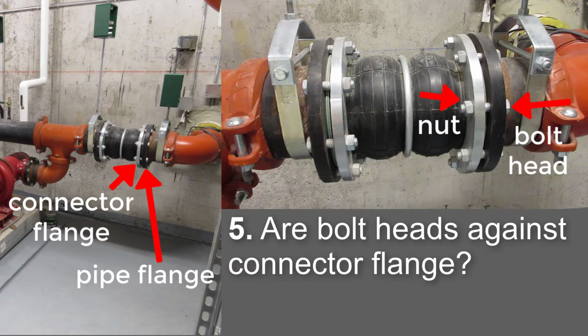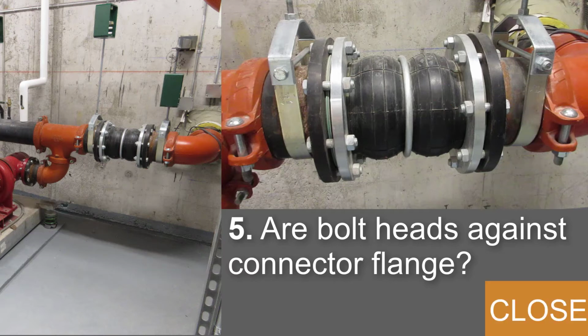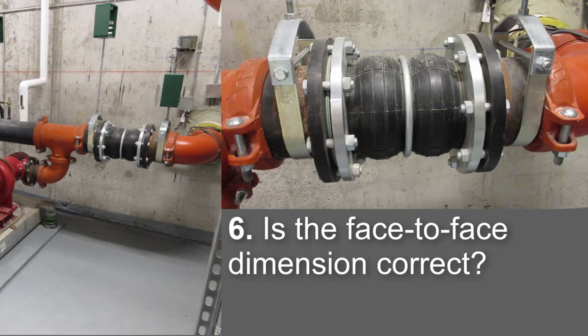In this case, there was no noticeable damage and the bolts were not long enough to touch the joint body, so this one is close enough. No need to get the contractor to reinstall these. Is the face-to-face dimension correct? The distance between the flanges is about 13 inches, as stated on the datasheet. The expansion joint isn't stretched or compressed, so it's okay.